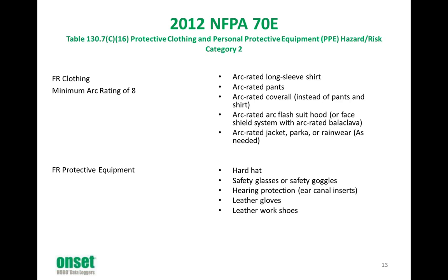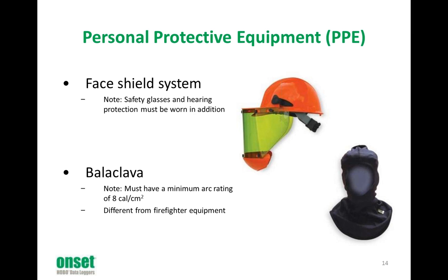So for hazard risk category 2, you want to make sure there's an arc-rated long sleeve shirt, arc-rated pants, arc-rated coverall, arc-rated suit, arc flash hood, and a jacket if you're working outside. For flame-resistant protective equipment, you'd need a hard hat, safety glasses or goggles, hearing protection, leather gloves, and leather work shoes. So we'll show you what each of those look like.